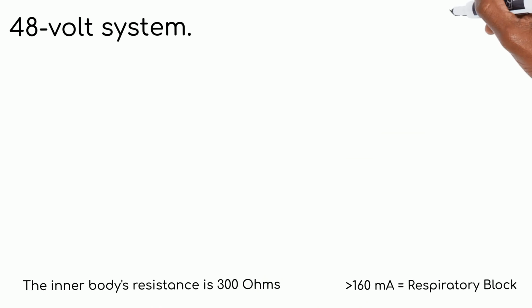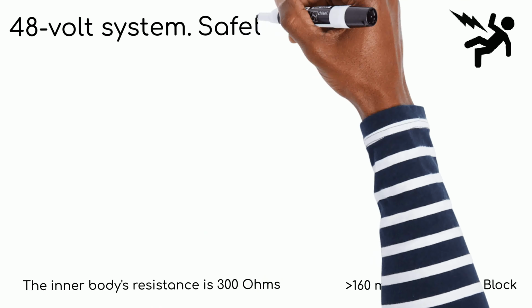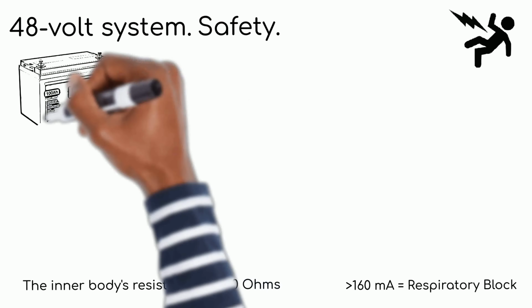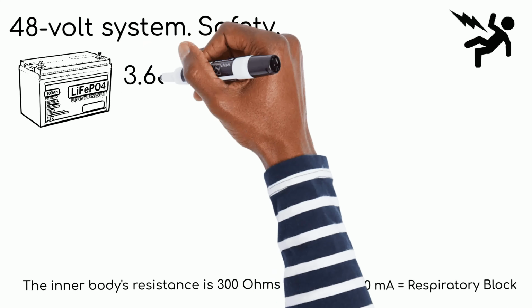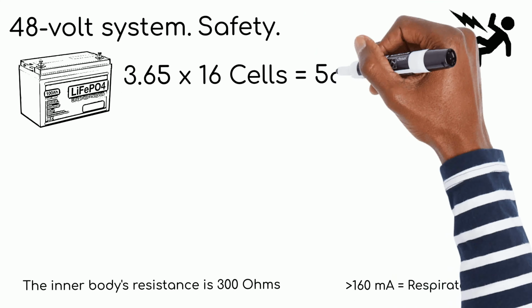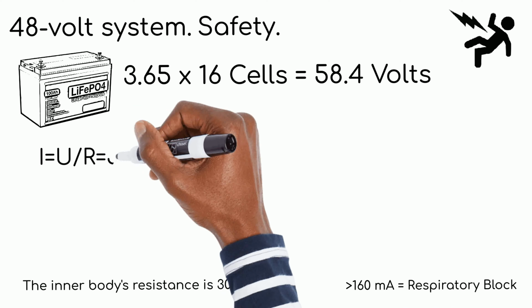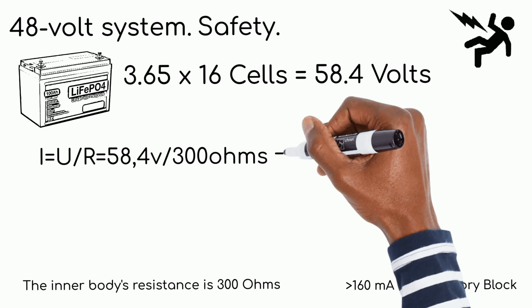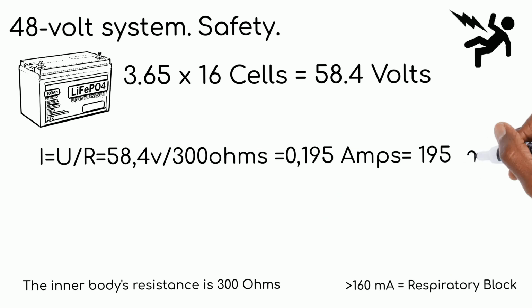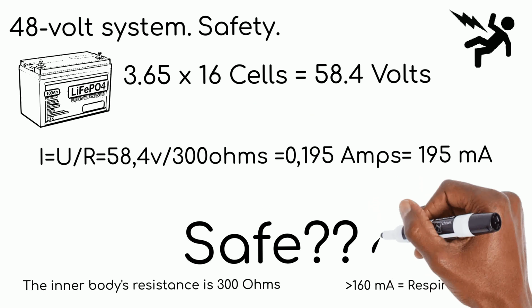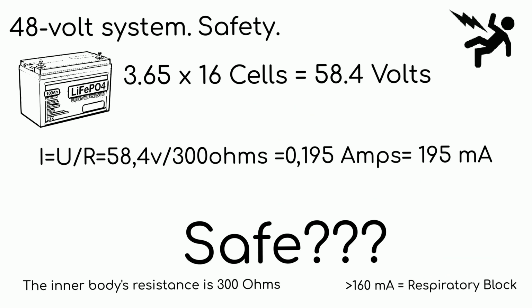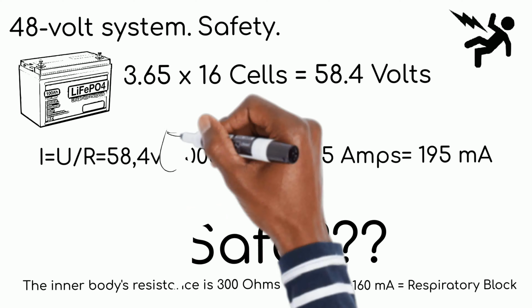48-volt system. Is 48 volts a safe voltage? In the case of LFP batteries, voltage can reach 58.4 volts and current potentially is 195 milliamps. So, 195 milliamps is more than 160 milliamps. This voltage is potentially dangerous under abnormal conditions, but is reasonably safe for most people under normal conditions.